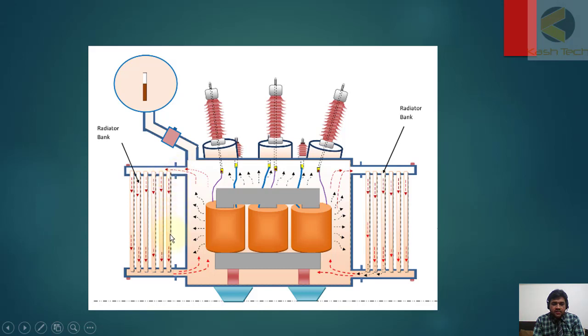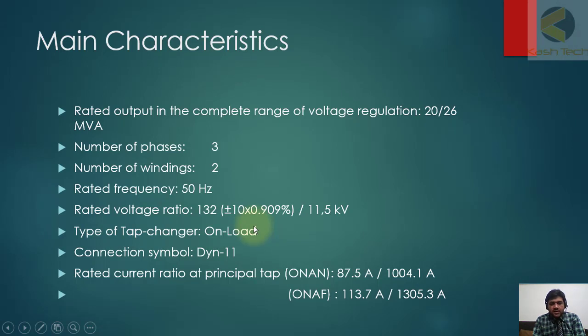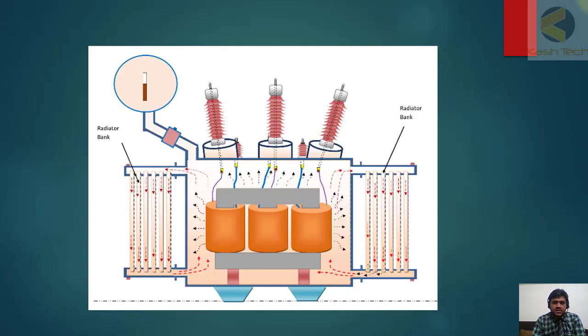The radiators have more surface area and are exposed to air, so the oil cools down and comes back — this is the natural circulation cycle. At the bottom, fans are connected to further increase the cooling effect. Another option is that a pump can be connected to force the oil to move faster through the radiator, increasing cooling further, but this is only used in big transformers.